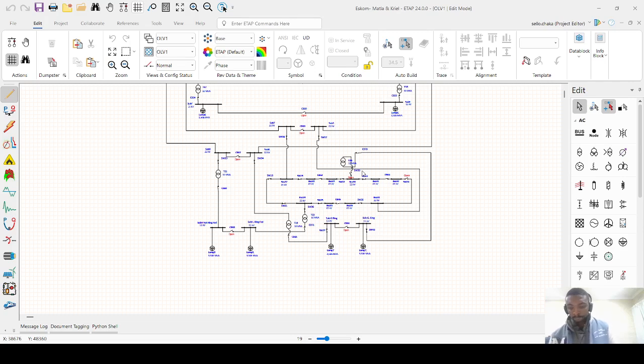The circuit breakers are installed on every feeder, for both the 22 kV and 11 kV substations, to isolate faults and perform safe switching during routine operations or during contingency operations, whereby sometimes when we lose one transformer feeder, we can still supply via the tie breaker in those scenarios.